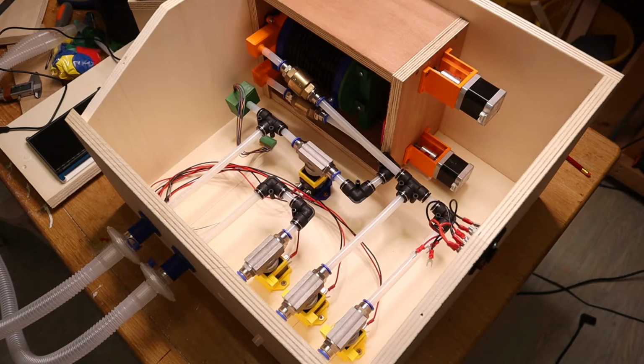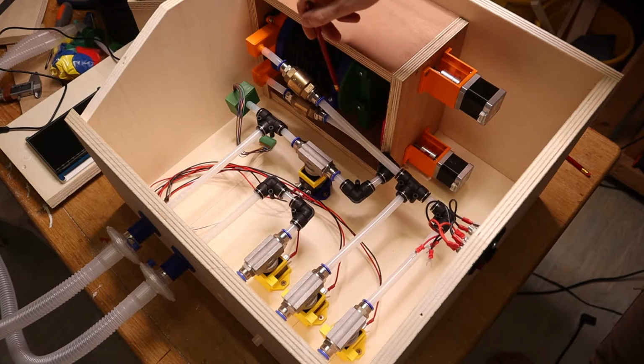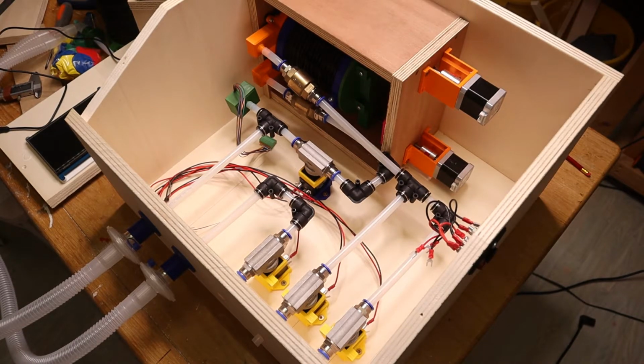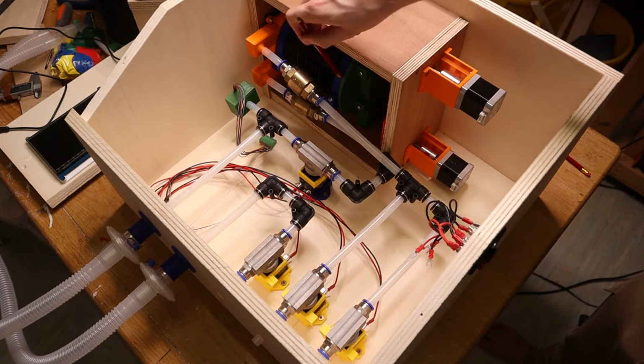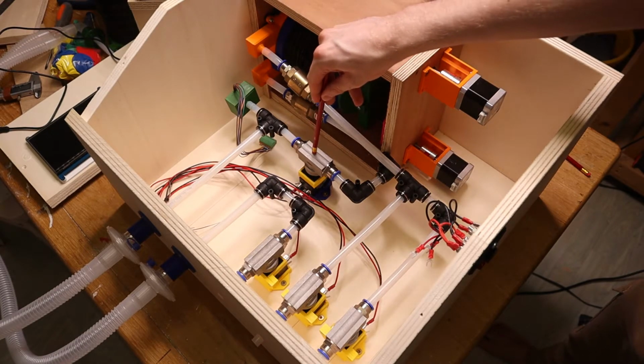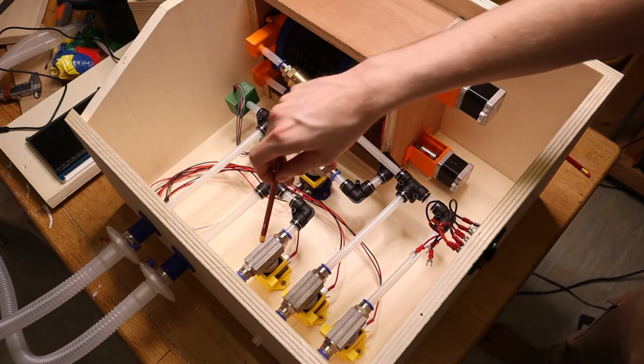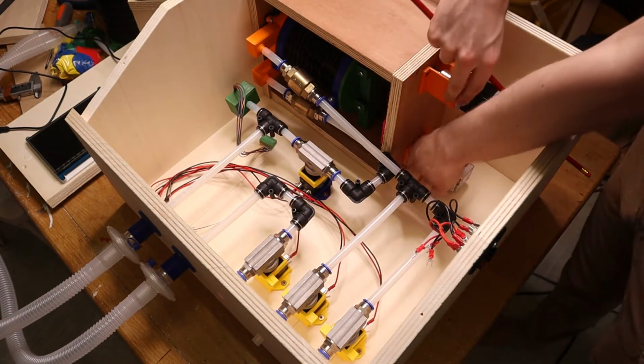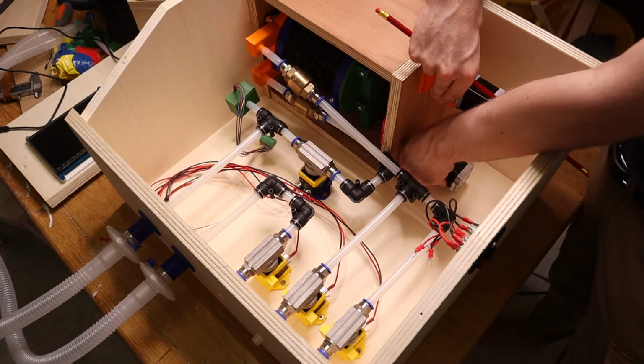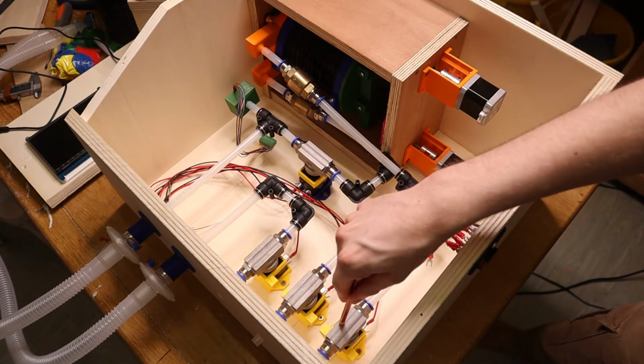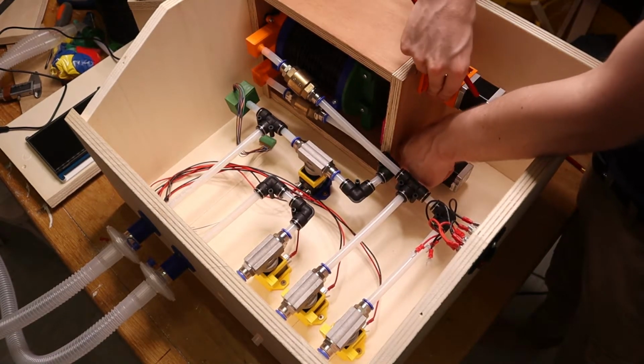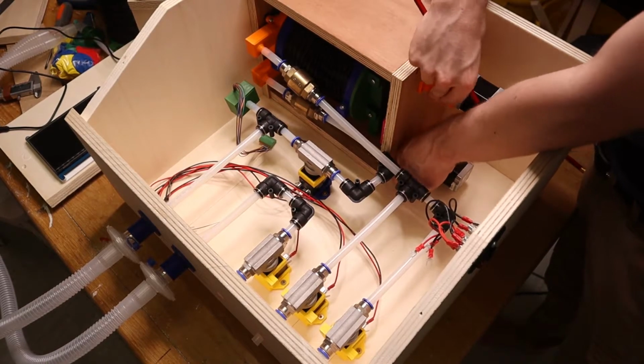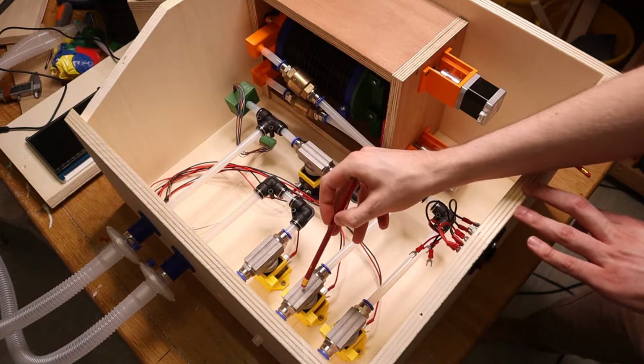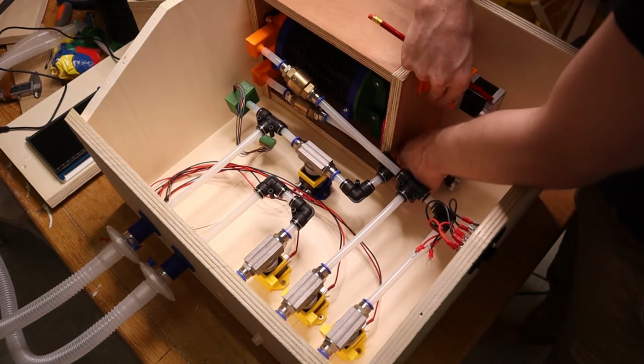So you can do this either in a volume targeted mode. In that case you can basically calculate how far you have to compress here. But I think with a PID loop or similar control loop, you can also do this with a pressure targeted mode. Whatever the case, once you reach the end of inspiration, you have to close the inspiratory valve and open the expiratory valve. And once you start doing that, the patient will start exhaling, and simultaneously the bellows pump will start to turn back. So what you do is you open the oxygen valve and you move the bellows back part of the way. And then you close the oxygen valve and you open the air valve, and then you move the piston up the rest of the way.